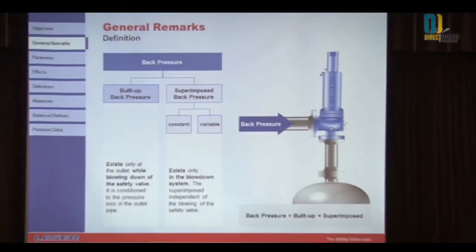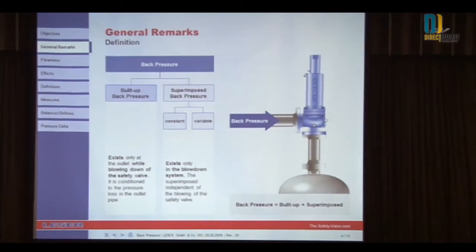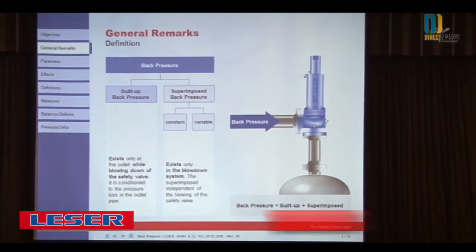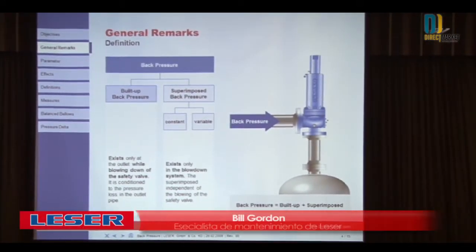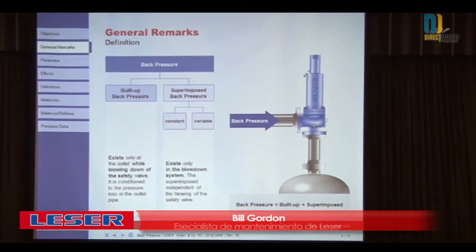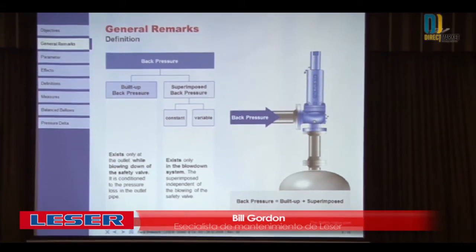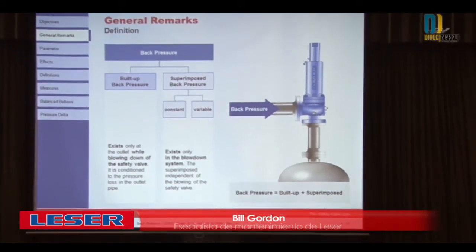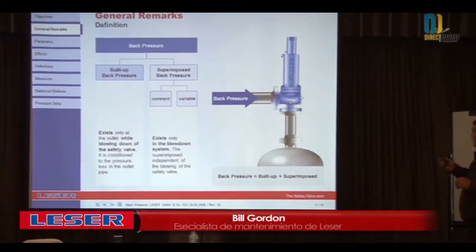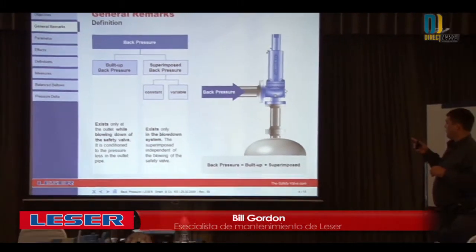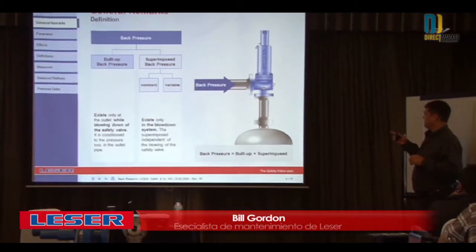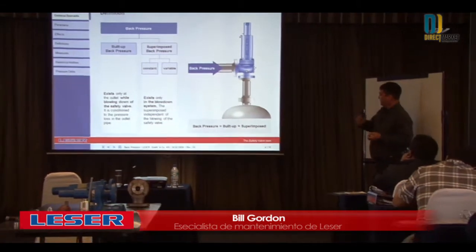There are two different types of back pressure: built-up back pressure and superimposed back pressure. Built-up back pressure exists only at the outlet while blowing down of the safety valve — so when the valve opens, it creates built-up back pressure.